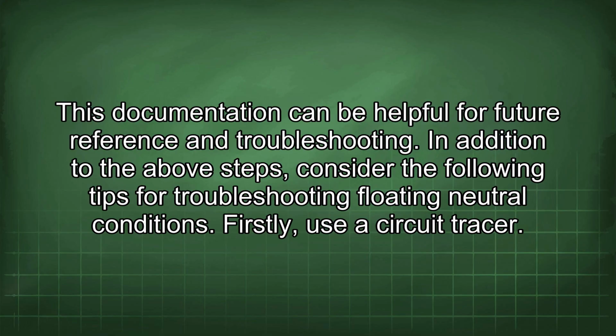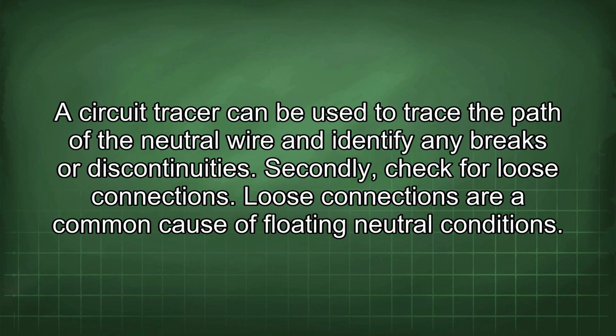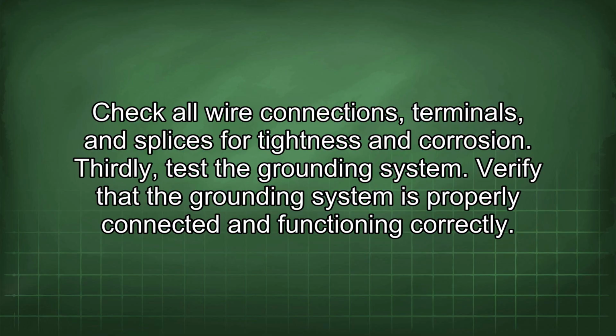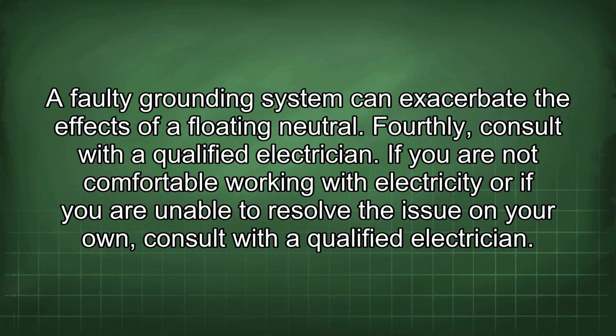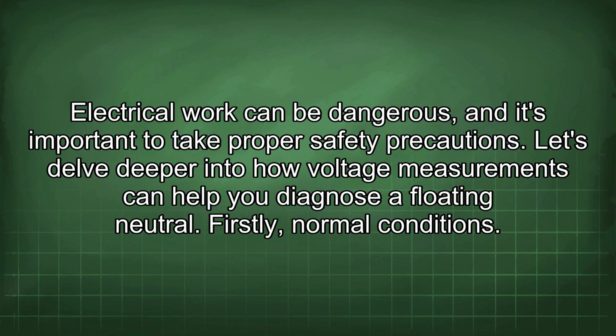In addition to the above steps, consider the following tips for troubleshooting floating neutral conditions. Firstly, use a circuit tracer. A circuit tracer can be used to trace the path of the neutral wire and identify any breaks or discontinuities. Secondly, check for loose connections. Loose connections are a common cause of floating neutral conditions. Check all wire connections, terminals, and splices for tightness and corrosion. Thirdly, test the grounding system. Verify that the grounding system is properly connected and functioning correctly. A faulty grounding system can exacerbate the effects of a floating neutral. Fourthly, consult with a qualified electrician. If you are not comfortable working with electricity or if you are unable to resolve the issue on your own, consult with a qualified electrician. Electrical work can be dangerous, and it's important to take proper safety precautions.